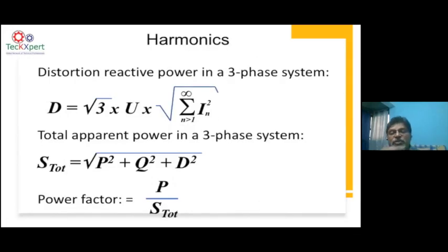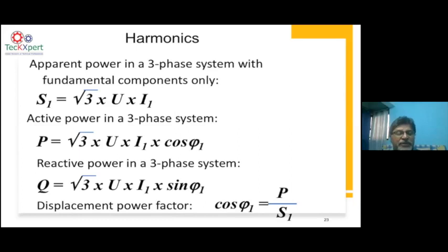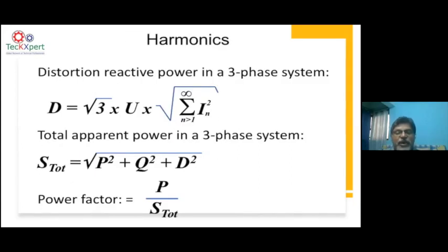Now, when there are distortions or harmonics in the network, the distortion adds a certain amount of reactive power. That is called distortion reactive power. So when you have distortion, your power factor comes down. The distortion reactive power, in addition to the fundamental wave reactive power, comes from all the harmonic waves, and we take that value as D squared. The power factor then involves P squared plus Q squared plus D squared, unlike the previous slide, which had only P squared plus Q squared. Because of that added D squared, when there are harmonics, the power factor comes down.